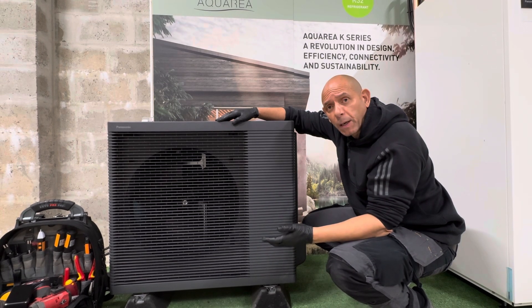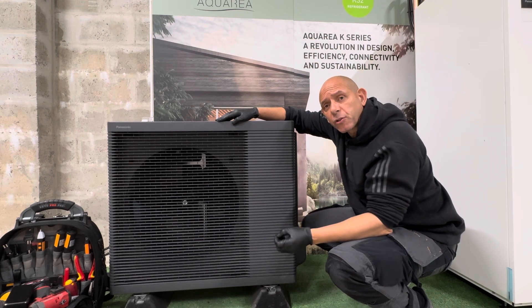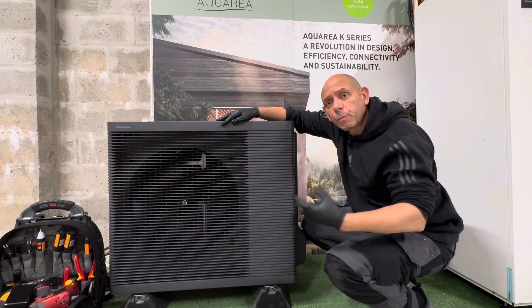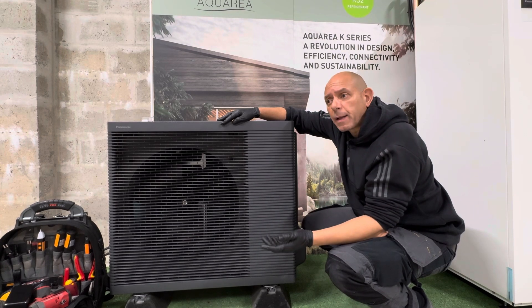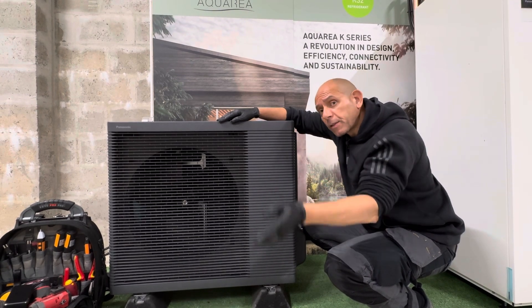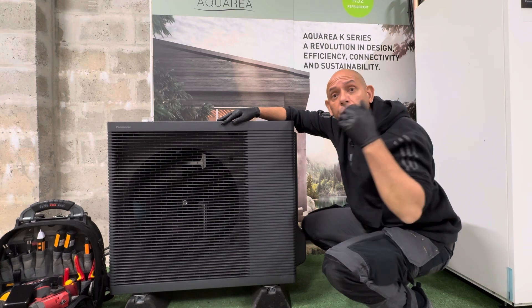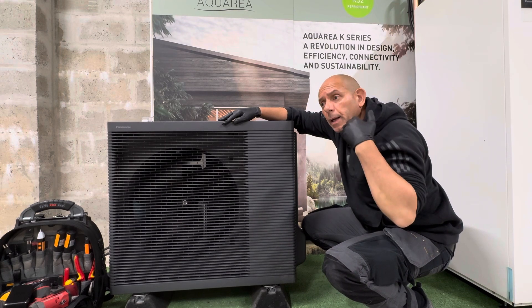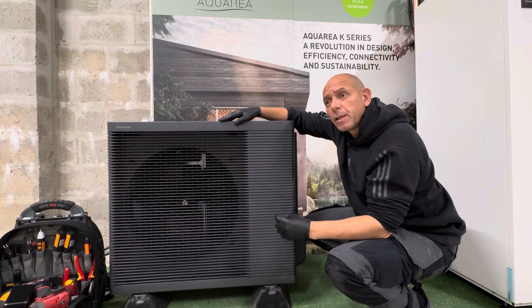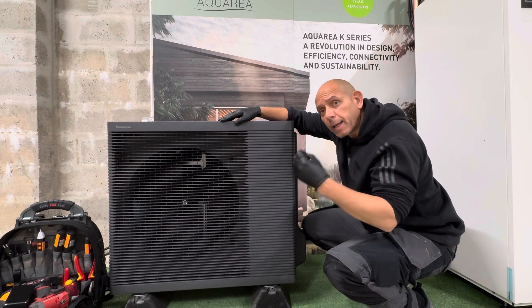With the bi-block option, you'd have the wall-mounted bi-block which contains the hydraulics, plus a Panasonic Aquarea hot water cylinder — either the 200 litre or the 300 litre. However, we have had clients who want a larger cylinder. In that instance, it has to be the K-Series with the bi-block and a third-party cylinder, such as a 400 litre. So you can go beyond the 300 litre Panasonic Aquarea cylinder — it just has to be third party, but it works exceptionally well. Just make sure it has a large coil inside the tank so you get high gain and high efficiency.